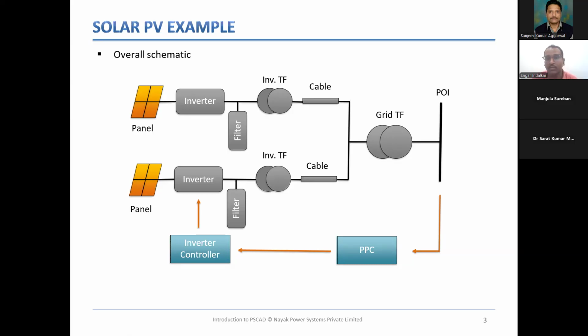Okay. Now, if you notice, this type of model is called a single machine infinite bus type system. Why? Because if I try to model everything, it becomes very difficult to model hundreds and hundreds of inverters. So we club them together, we aggregate the entire plant into a single energy generation source, which is what the grid utilities want. They want a simple representation of the entire plant as one energy generating source. So we have to aggregate all this into a single generating source so that the behavior of the plant can be studied.